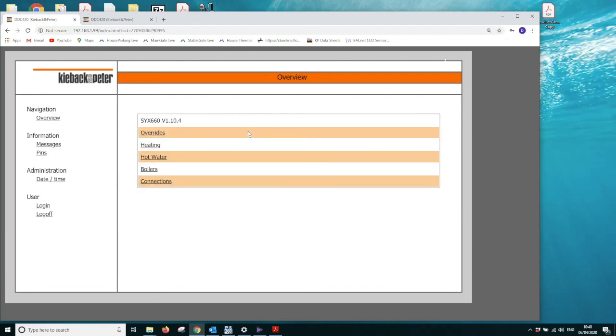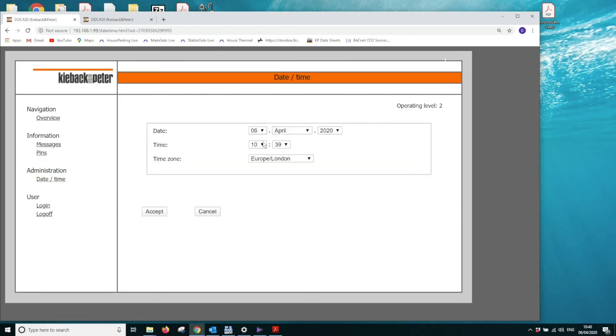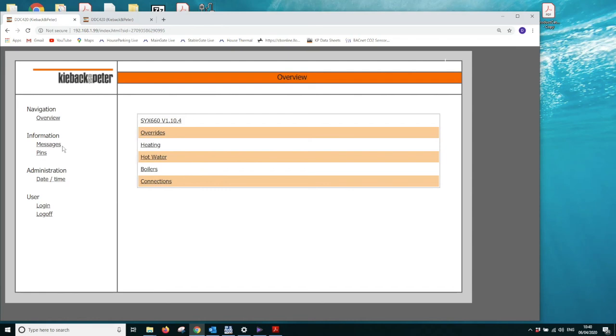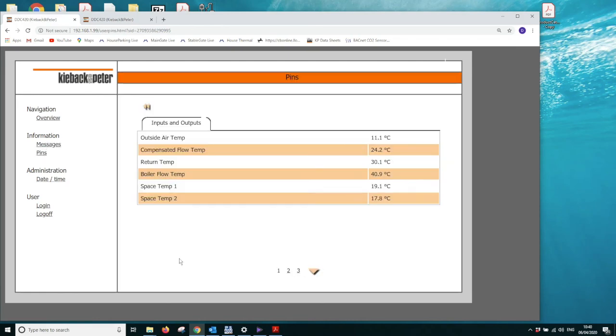This is quite nice from more of an engineering perspective. We can do a few extra things that we can't do on the MO browser, such as adjust the date and time. We can set the time zone and set the time and date should there be a slight bit of drift, or you may need to make some changes based upon maybe fitting in a different country. We can look at the pins which are live on the controller. This is a lot better for commissioning. Saves you dropping in and around different menus to look at what the condition of the inputs and outputs are. So obviously here you can see all the sensors, you can see what the current condition of the outputs are, which is quite nice. So it helps you do some fault finding if there are some little debugging things to go through when you're doing the wiring.